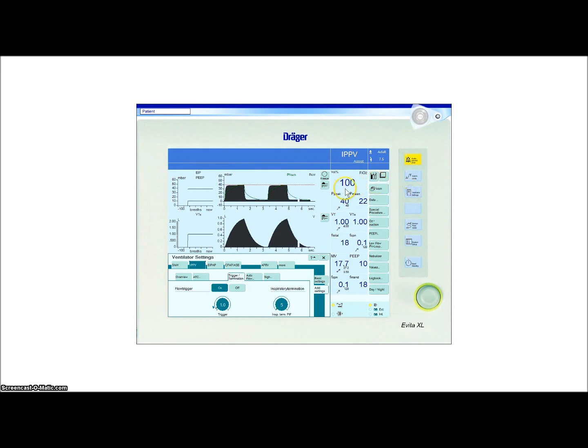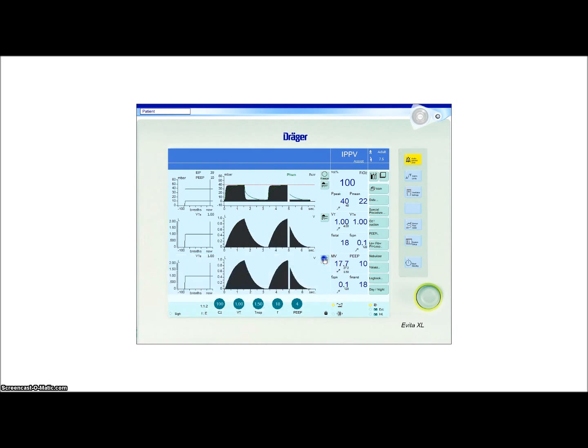The Evita XL is in IPPV. This patient has no spontaneous effort, so we are delivering a rate of 18. He is getting a mandatory rate of 18. The only reason we have a spontaneous rate of 0.1 is because the ventilator is just trying to equilibrate. This is the pressure waveform. There's a volume waveform. If I turn this off, we'll put the flow waveform down here.